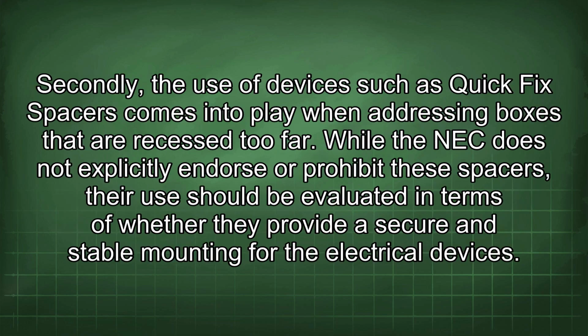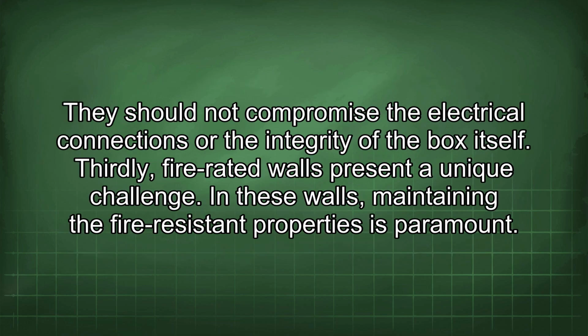Secondly, the use of devices such as quick-fix spacers comes into play when addressing boxes that are recessed too far. While the NEC does not explicitly endorse or prohibit these spacers, their use should be evaluated in terms of whether they provide a secure and stable mounting for the electrical devices. They should not compromise the electrical connections or the integrity of the box itself.